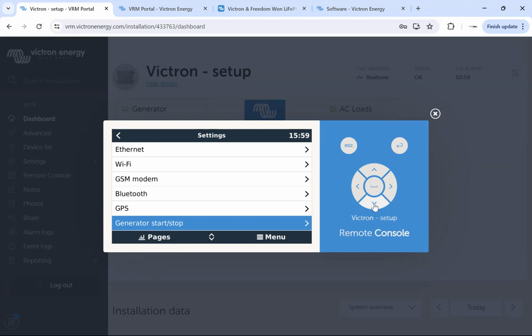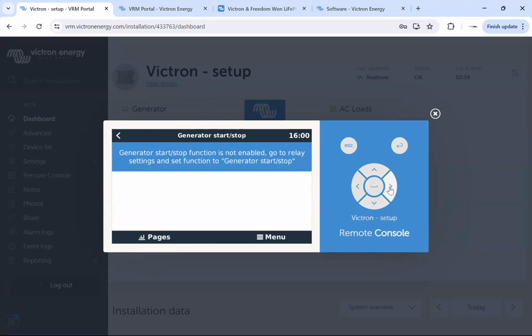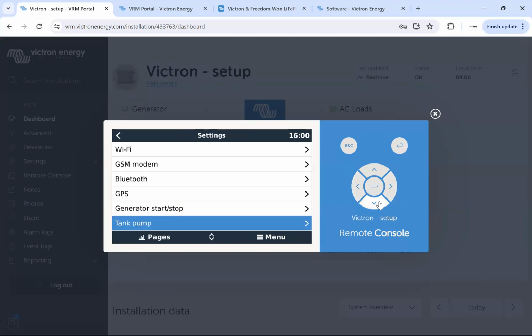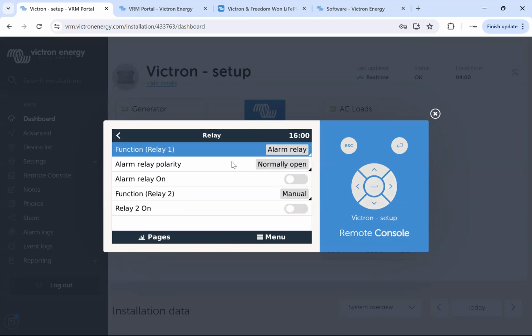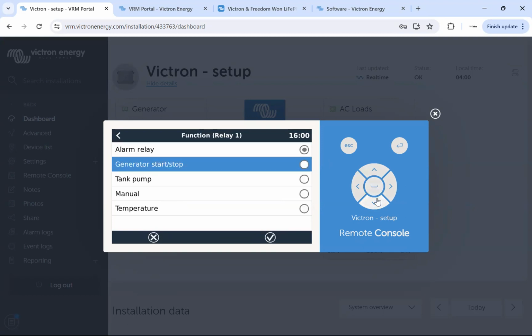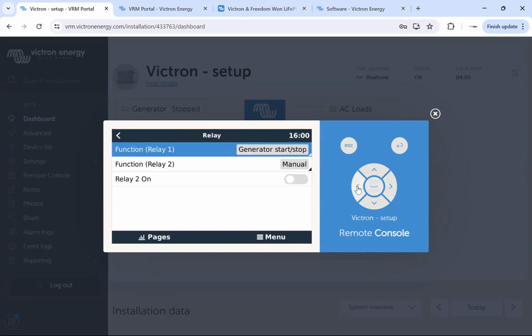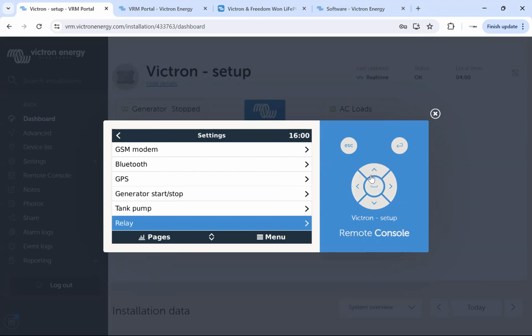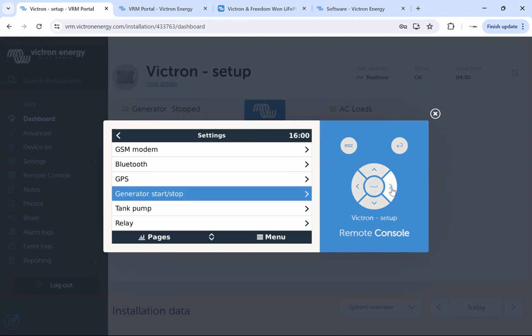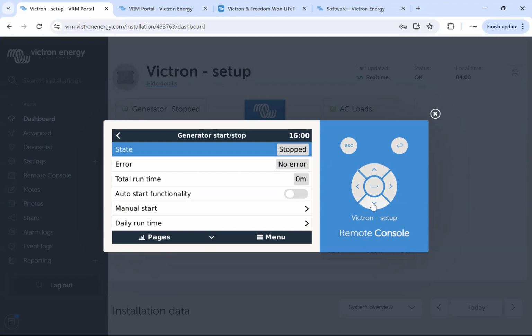Generator start stop, very important, but we can't actually access that. If you go like this, it says function is not enabled. Go to relay settings, set the function, then come back to this. Tank pump, we're not going to do that. Relay, there it is. So relay 1 at the moment is set to an alarm relay. So we want to set that to generator start stop. There we go.